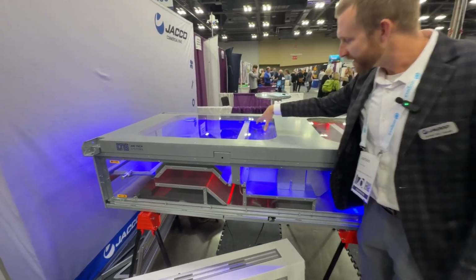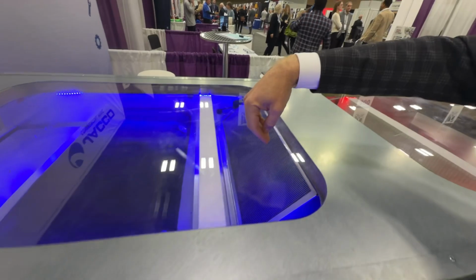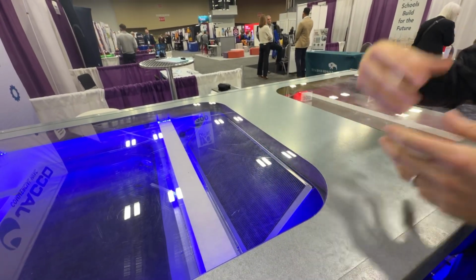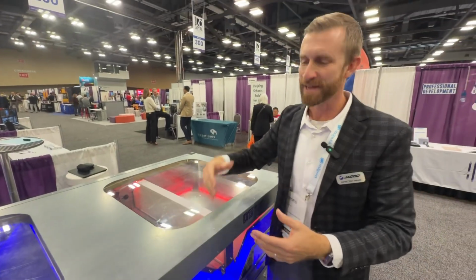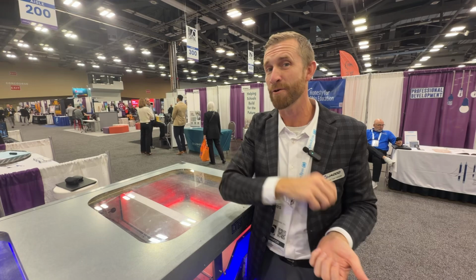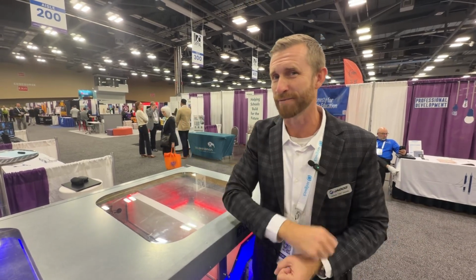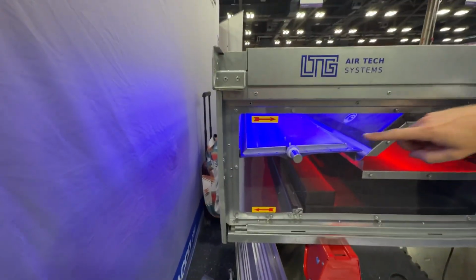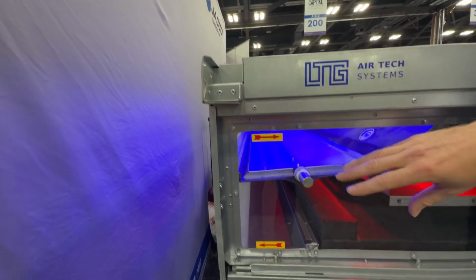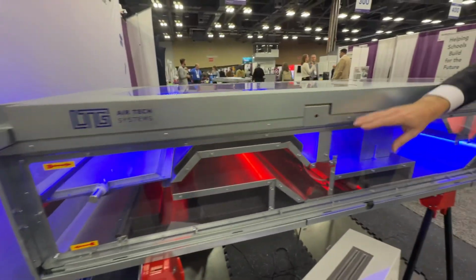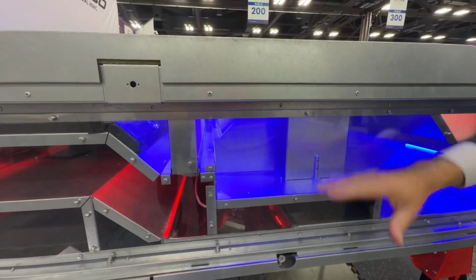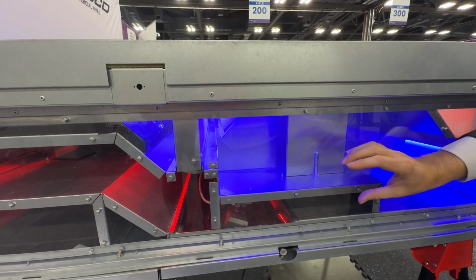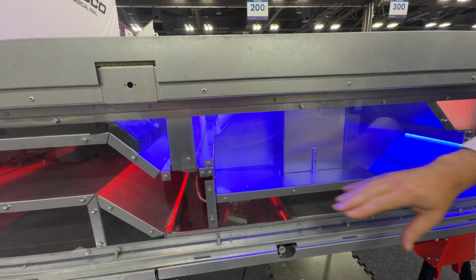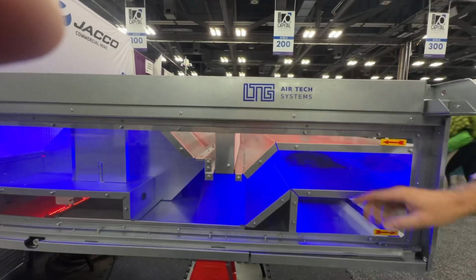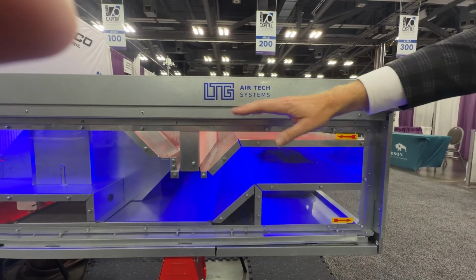Up here you can see down into this. This is a heat exchanger. Individual fins here will move air through it. Essentially, if you picture my fingers as tubes, you would see how that air is crossing but not being contaminated. So all of your fresh air is completely fresh air, and it is brought in at a 75% efficiency, so that at 0 degrees, that is not using 2 tons of heating and cooling. It's using a fraction of that. You see these arrows here, this is an example of where your cold air will be coming into the building. There's a fan here that's going to be exhausting the bad air and bringing in the good air. As that good air comes across, it's going to hit that heat exchanger and slide down. In that section is where you're getting that 75% efficiency gain by using the air you've already heated to temper the air coming in. And as you continue to follow the path, you can see that air is coming out and going into the classroom here. So exhausted air out, clean air coming in.